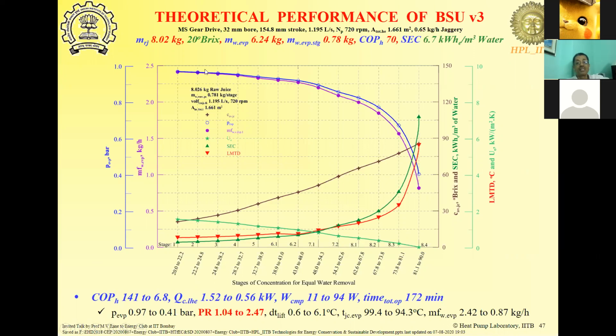So you can see that various parameters are plotted here, how the pressure starts dropping as the solution concentration keeps increasing. And the moisture removal also can be seen from here. Okay, the amount of moisture removed is here. So this color, if you see, says this. Initially, going from here to here, a lot of moisture is removed. But as you go towards the final stage, the amount of moisture removed is quite small. So most of the water gets removed in the early stages, where the pressure ratio is low and the solution concentration is low.